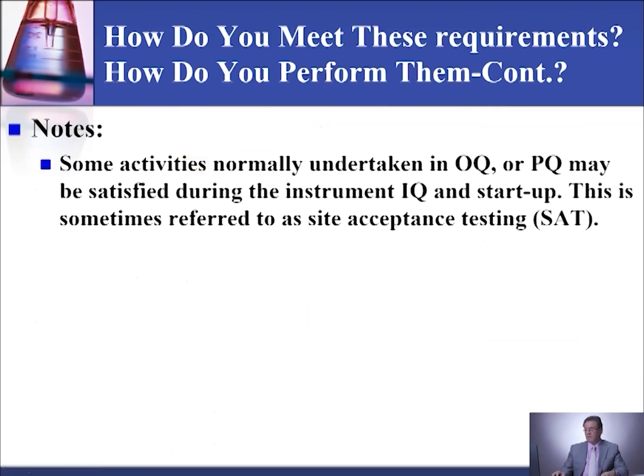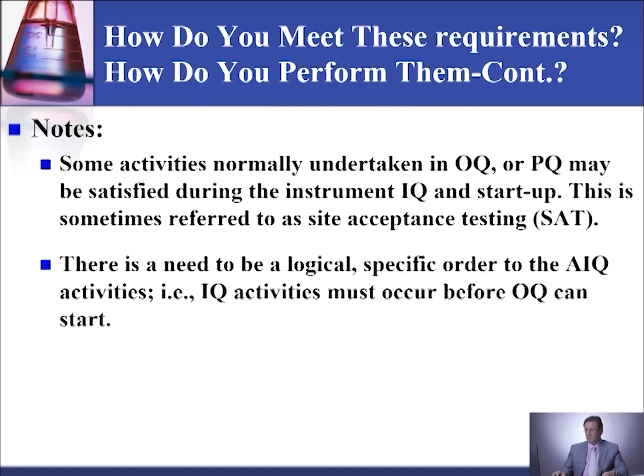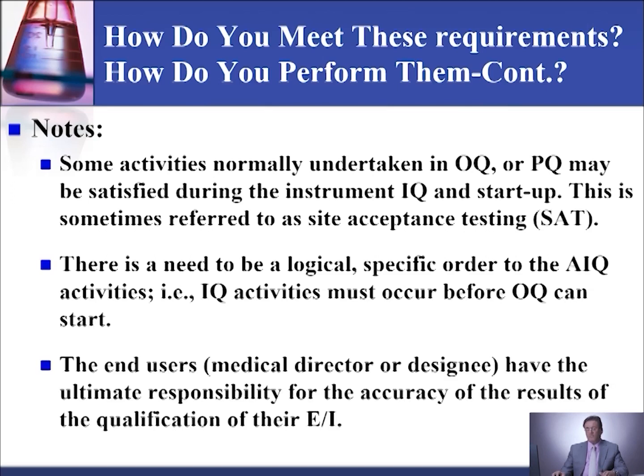Some notes regarding the process. Some activities normally undertaken in the operational qualification or performance qualification may be satisfied during the installation and startup of the instrument. This is sometimes referred to as site acceptance testing. There needs to be a logical, specific order to the qualification activities. For example, installation activities must occur before the operational qualification can start. The end user, which means the medical director or designee, has the ultimate responsibility for the accuracy of the results of the qualification of their equipment or instrument.